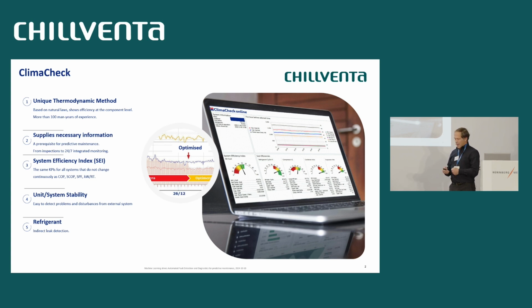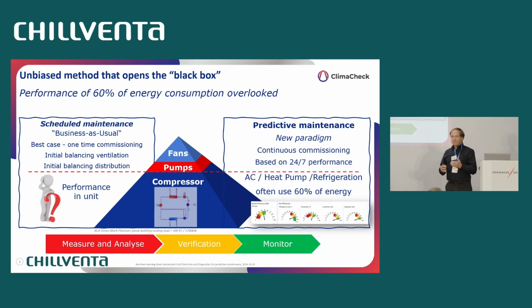And of course, a lot of things are happening now. We started online monitoring in 2007, and now predictive maintenance is on everybody's focus. And I think it's going to change the industry totally. Traditionally, there is a black box of the refrigeration process. Nobody's looking inside except for when somebody once or twice a year comes out and checks that it doesn't trip. But there is no focus on performance. Nobody is responsible for how the system operates in most cases.